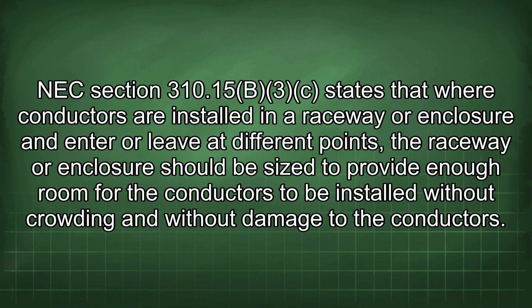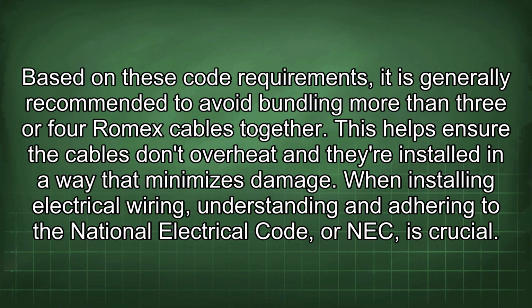NEC Section 310.15(B)(3) states that where conductors are installed in a raceway or enclosure and enter or leave at different points, the raceway or enclosure should be sized to provide enough room for the conductors to be installed without crowding and without damage to the conductors. Based on these code requirements, it is generally recommended to avoid bundling more than 3 or 4 Romex cables together. This helps ensure the cables don't overheat and they are installed in a way that minimizes damage.